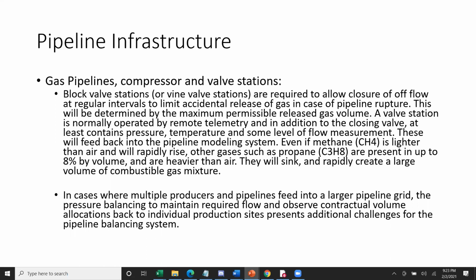Even if methane is lighter than air and will rapidly rise, other gases such as propane are present in up to 8% by volume and are heavier than air. They will sink and rapidly create a large volume of combustible gas mixture. In cases where multiple producers and pipelines feed into a larger pipeline grid, the pressure balancing to maintain a required flow and observe contractual volume allocations back into the individual production sites presents additional challenges for the pipeline balancing system.